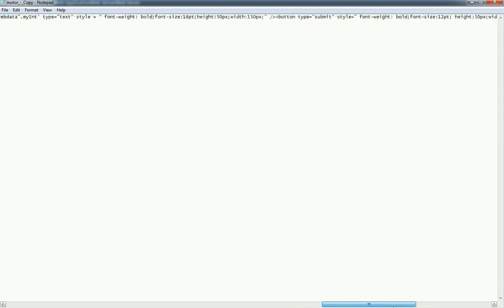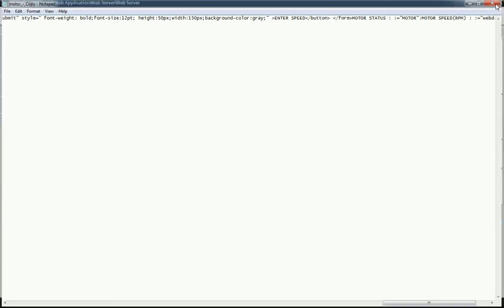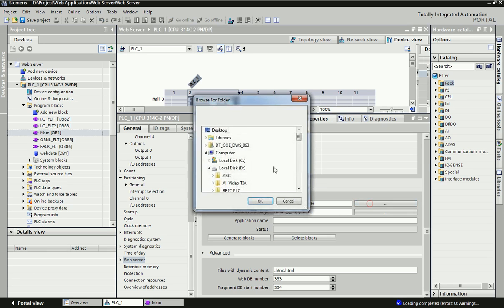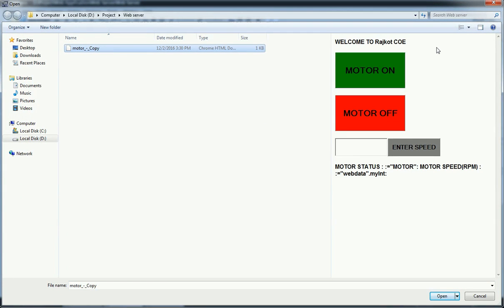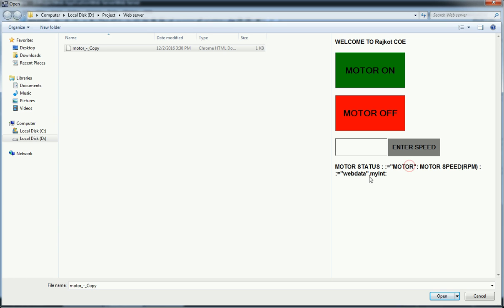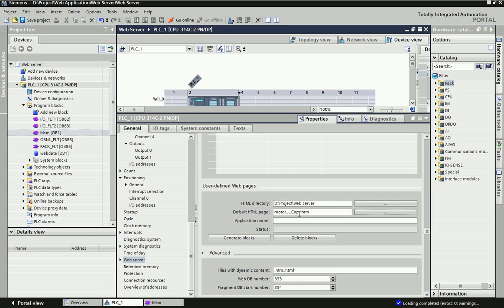From the HTML directory you can provide the path where you have stored the HTML file. Just click on the button and this HTML file will be linked with the application. When you click on the HTML file you will get a preview of how it will look in the browser. I have taken motor on and off buttons from the HTML coding. The variable 'web_data.my_integer' is my integer variable and 'motor' is my boolean variable, and I will define the PLC tags motor and my_integer accordingly.